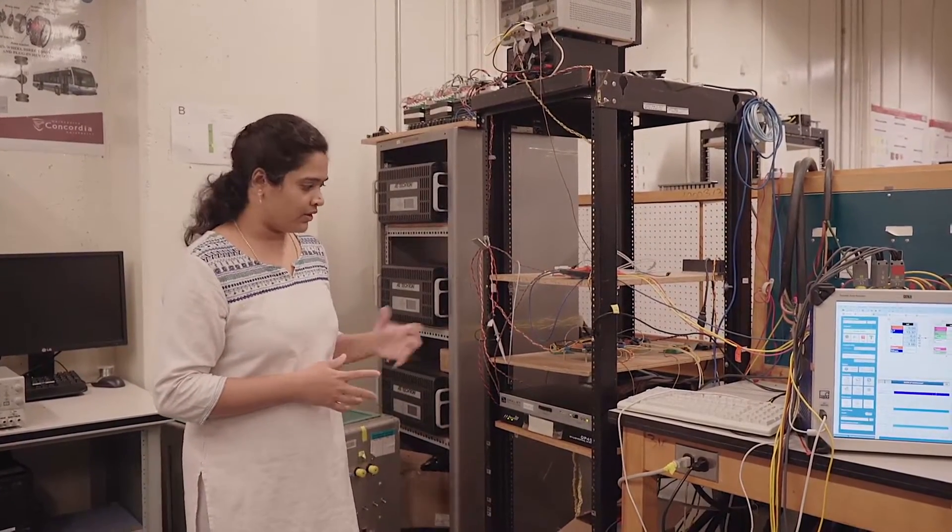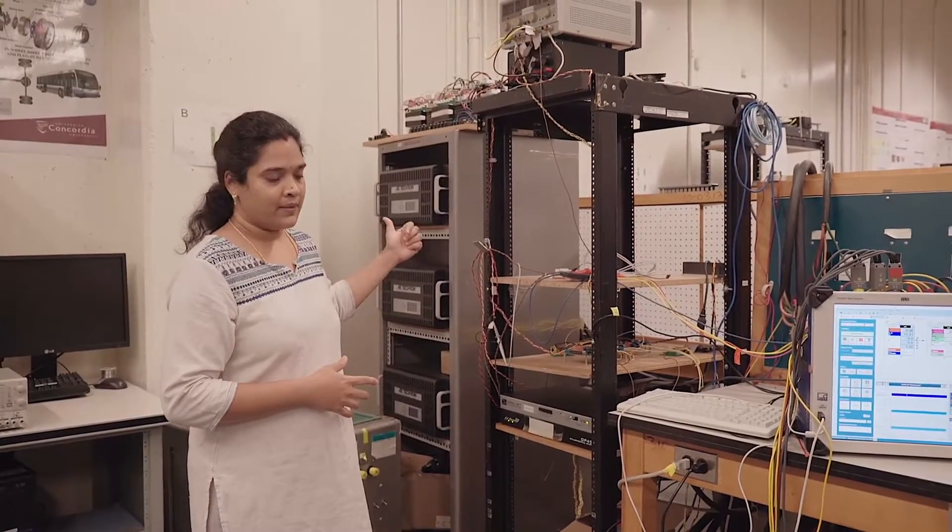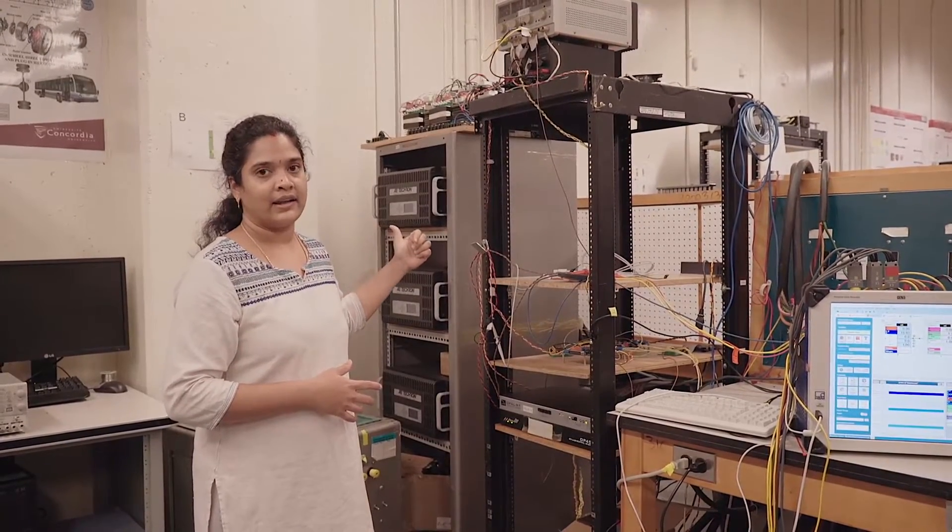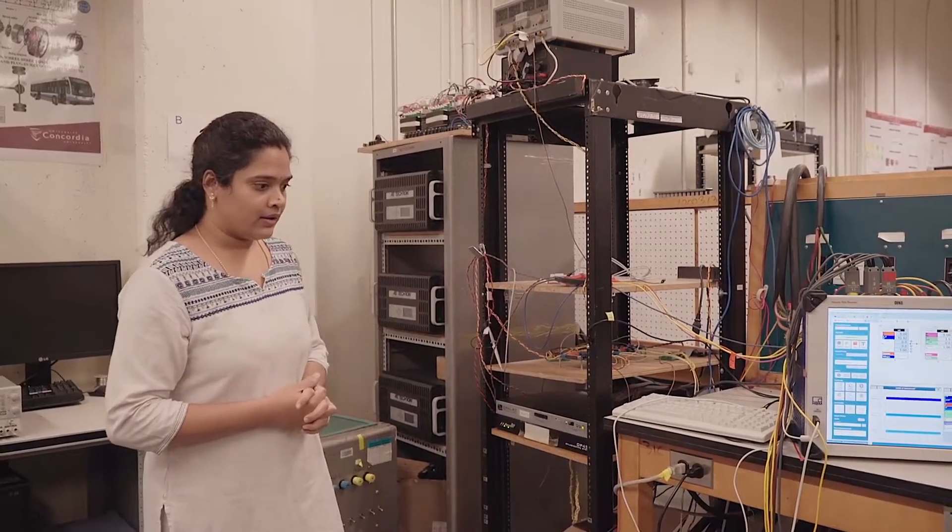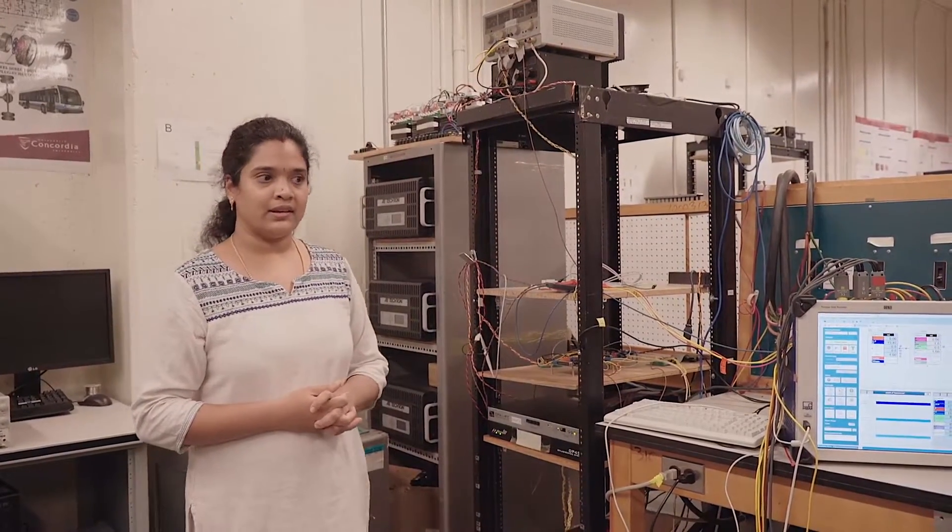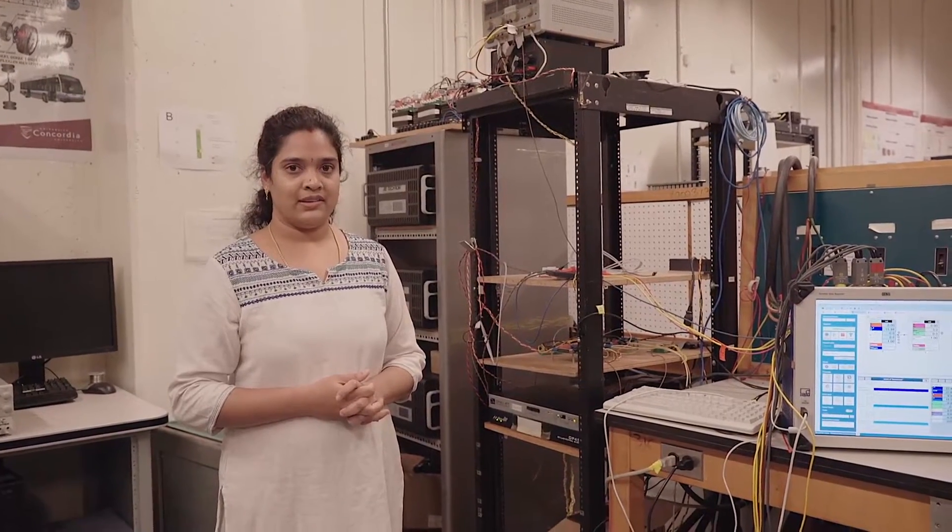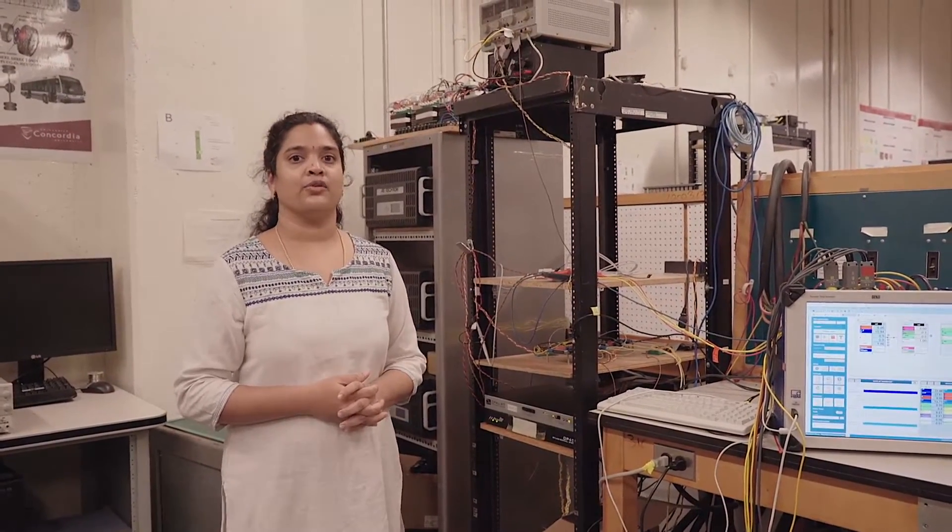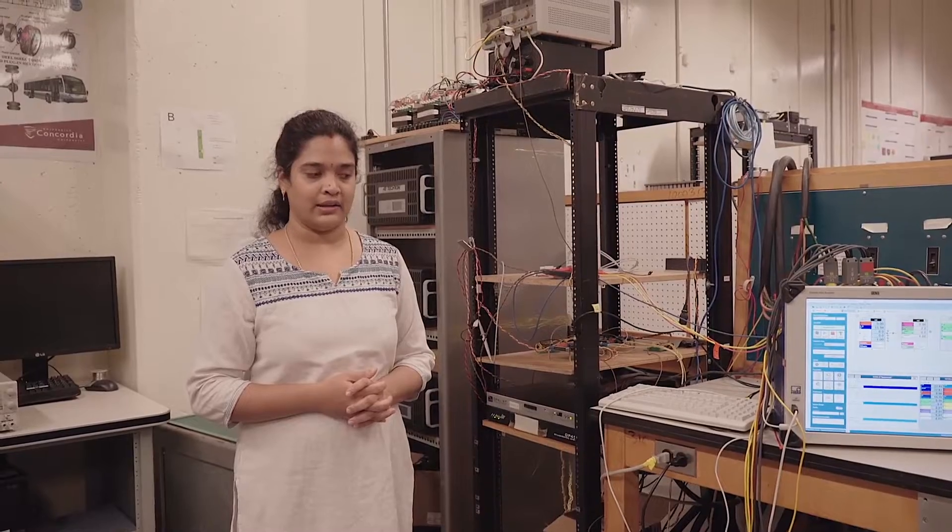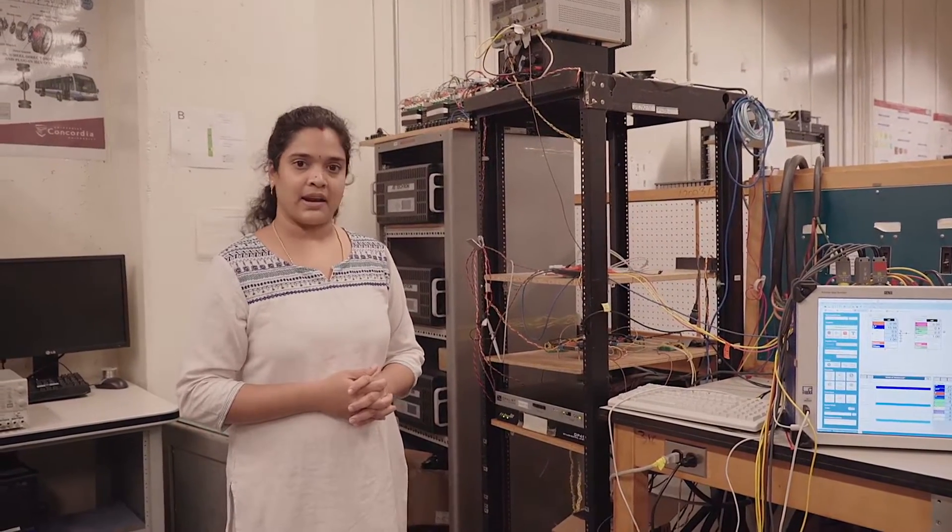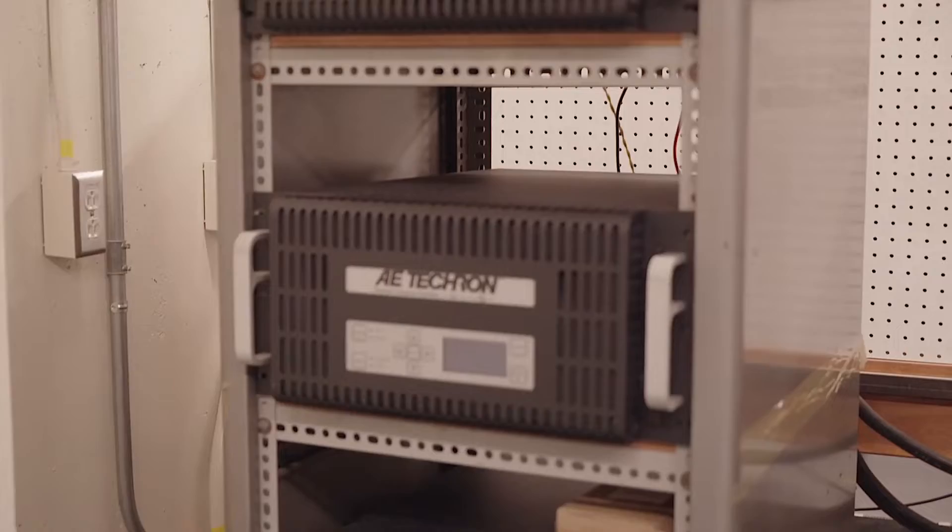This Opal RT is going to give control signals to the linear amplifier to behave exactly like a real induction machine. Here what I am doing in this setup is I am basically emulating some grid transients like short circuit faults and the open circuit faults in the grid and I am emulating the transients how the motor behaves to such transients.